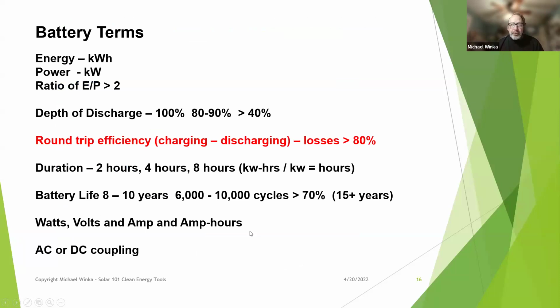Batteries also have a limited depth of discharge. You're not getting 100% of what you put into the battery out of the battery. You're typically getting 85%. Newer batteries, the lithium iron phosphate batteries, are getting 90+% depth of charge. And that's related to the round trip efficiency. You're losing something when you charge it, you're losing something when you discharge it. So those are things to think about when you're looking at a battery system. It's also about the duration of that system. So you have 2, 4, 8 hour durations. How you can calculate that is the energy divided by power gives you the number of hours. We'll talk about how long you can run the battery in power versus energy in a couple of examples in some slides. Battery life is typically pushing upwards of 10 years now, 10,000 cycles. They're probably lasting 15 years plus. I mean, your battery in your car, the Tesla batteries have been coming out with 200,000 miles.